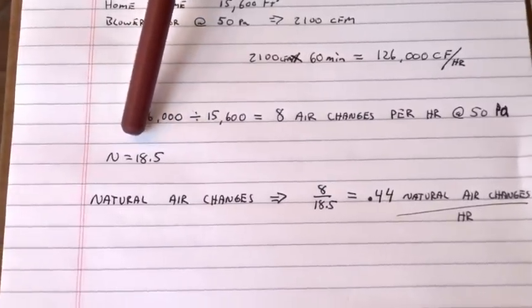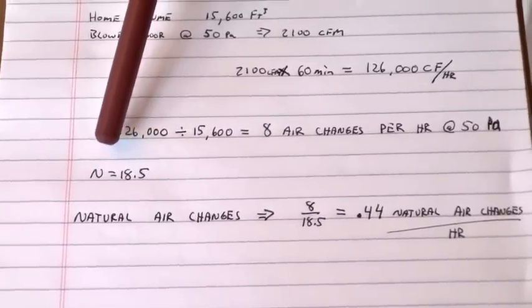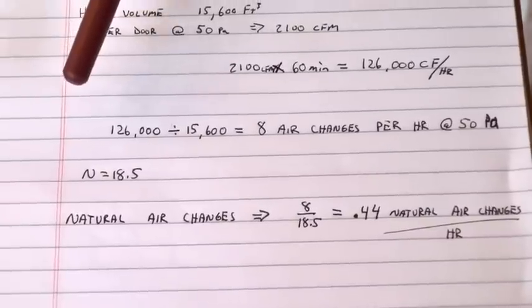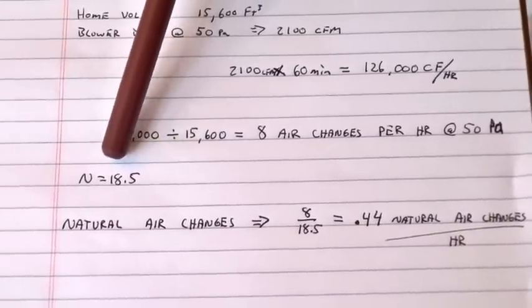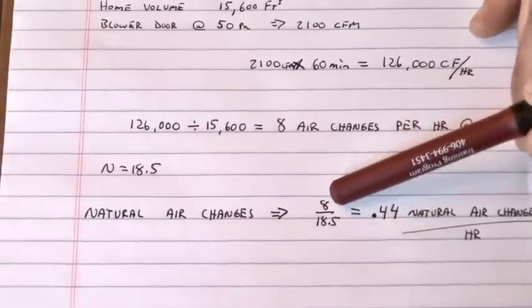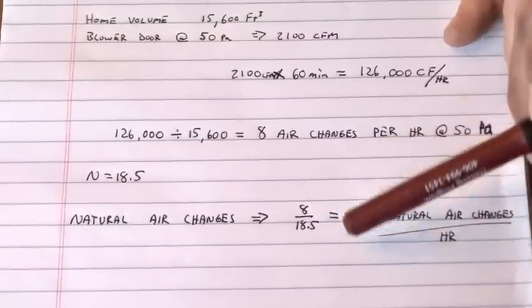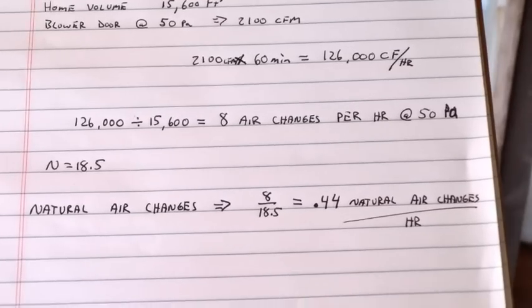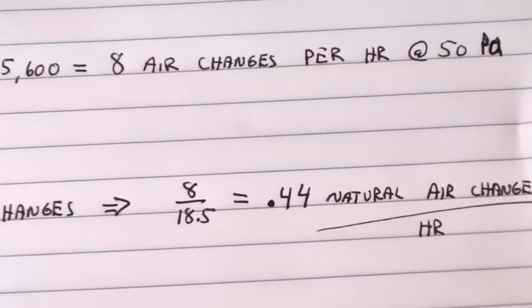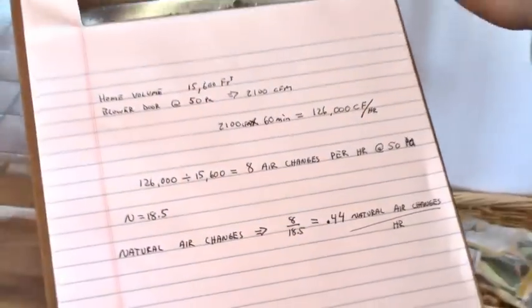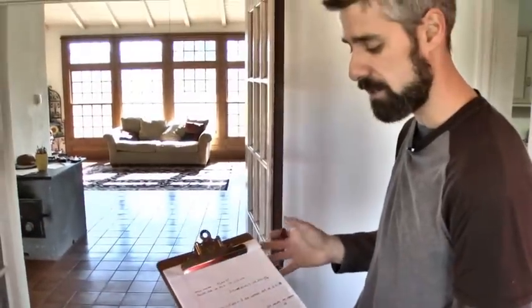Every area has an N value to calculate the amount of natural air changes — meaning if there's no wind on your house and you don't have a blower door set up, that's how many air changes you get naturally. The N value for our area is 18.5. So I take eight air changes per hour at 50 pascals and divide by our N value of 18.5, and I get 0.44 natural air changes per hour. The target — the tightest you really want to get a house, at least based on our standards — is about 0.35 air changes per hour. So 0.44 is really not all that bad.